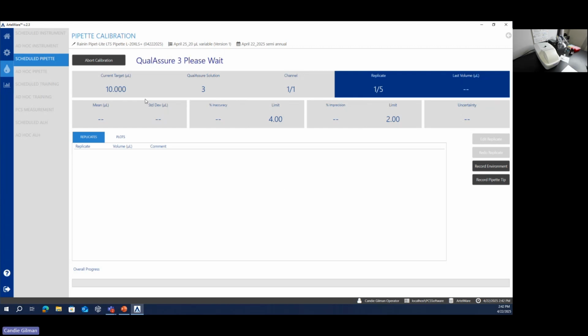So I want to bring your attention back to the software for just a moment. The software is showing me a lot of useful information. So it's telling me that I'm currently testing 10 microliters, Qual-Assure 3 solution. It's a single channel device. I'm going to take 5 replicates. And here are those preloaded tolerances that I loaded in earlier. And so now the system is asking me for pipette sample number 1. So I'm going to go ahead and just pour out an aliquot of this solution.